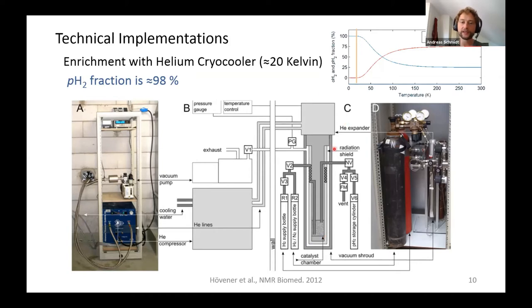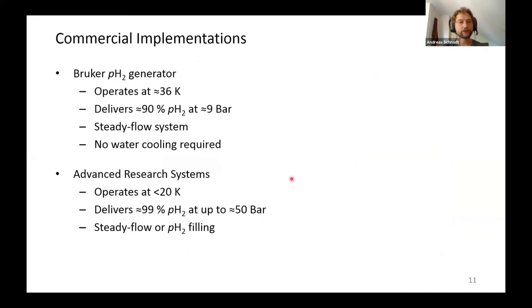A very similar setup also uses a helium cryo-cooler, with a special requirement for clinical installation: all electronics were inside the building while all explosive parts were installed outside, separated by a wall. A cooling finger is cooled to 20 K, hydrogen passes through the catalyst chamber, and the system delivers 98% parahydrogen, which can be filled into gas bottles for experiments. This type of system is also commercially available, including the Bruker system operating at 36 K, delivering approximately 90% parahydrogen at up to 9 bar in a steady-flow configuration.